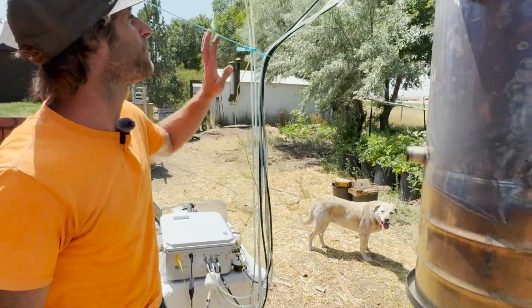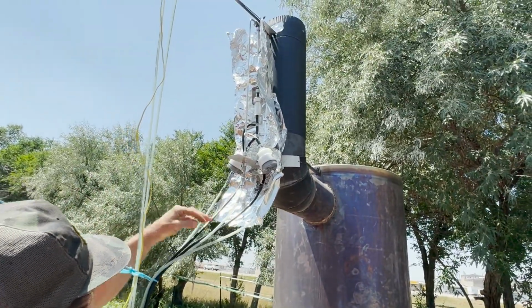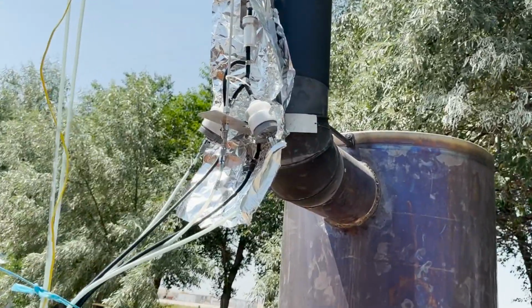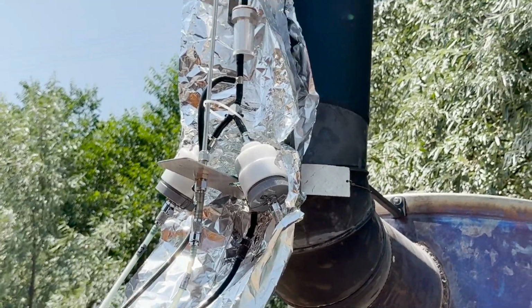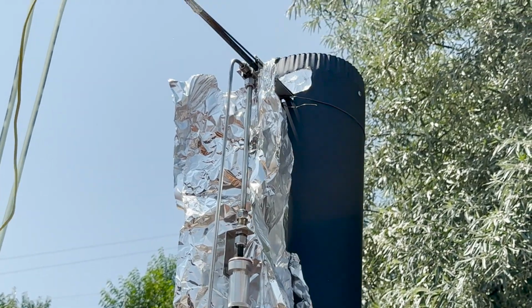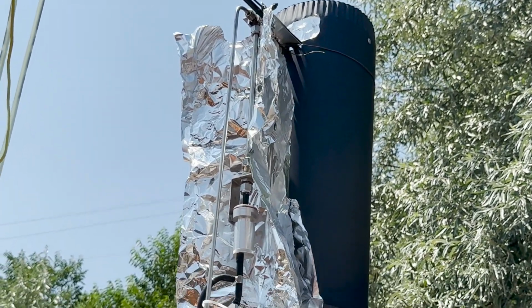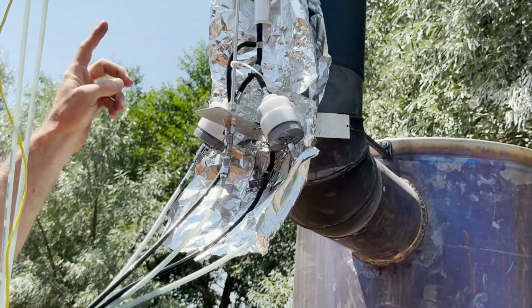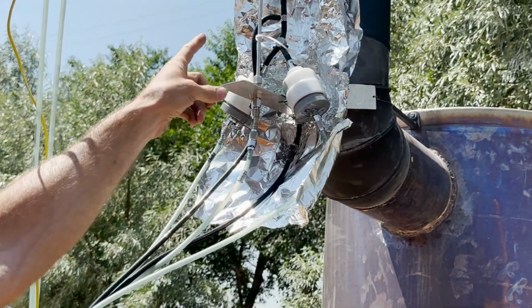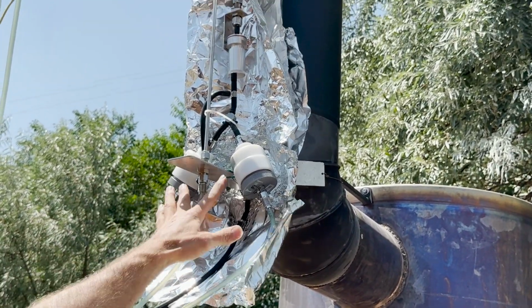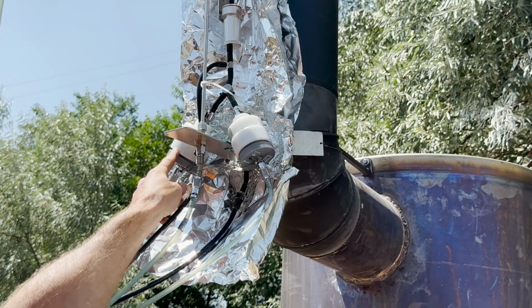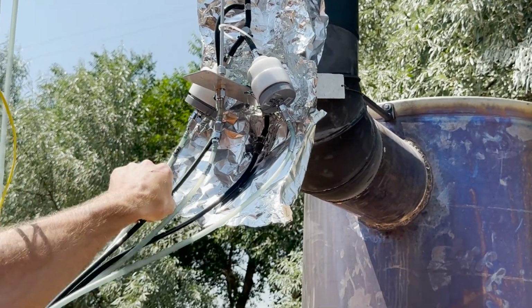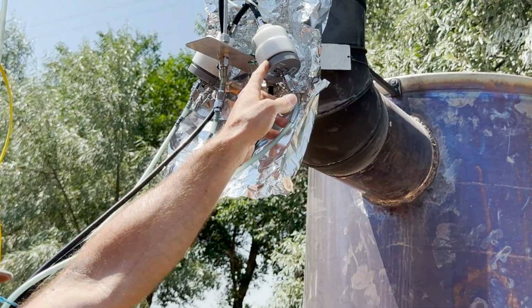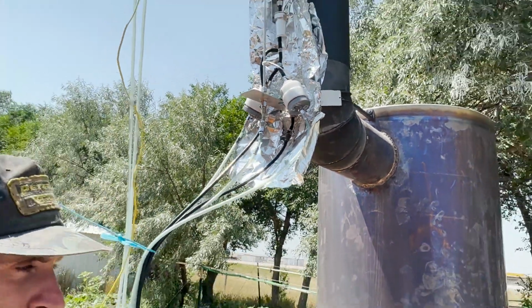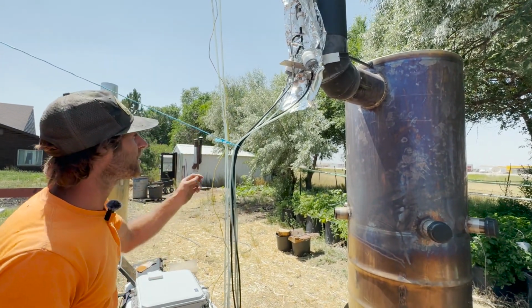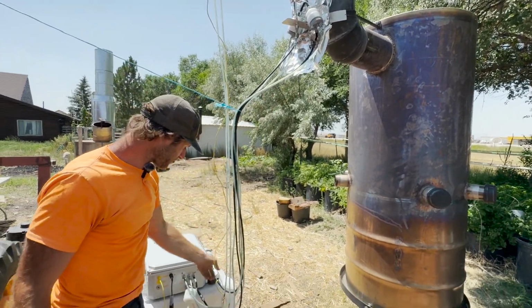If we look up here at the probe, we have the dilution air going up this line. It's hard to see because we have the foil in the way, but this probe was designed for an insulated chimney, and this chimney is not insulated, so we had to add a heat shield to keep things cool. The dilution line goes up and mixes with the sample, and then the diluted sample comes down the other line. It goes through the PM 2.5 particle separator, and then it splits. One sample goes to this filter, one sample goes to this filter, and a third sample line comes down to go to the gas sensors. One filter is gravimetric to measure the PM mass. The other filter is a quartz filter to measure the particle composition. And then the undiluted sample line here comes out to go straight into the instrument.